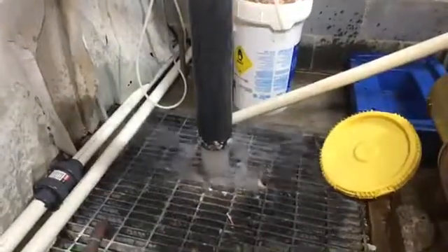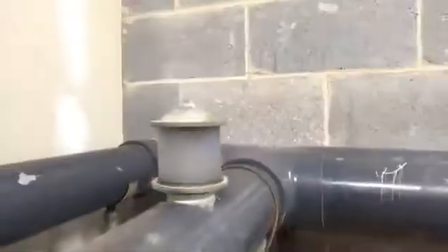We're here in North Carolina and we are currently backwashing this filter. We just did a deep cleanse and a deep purge with enzymes and phosphate remover, and that water looks pretty nasty. You can see that sight glass up there, and you can actually see some of it kind of moving out here.